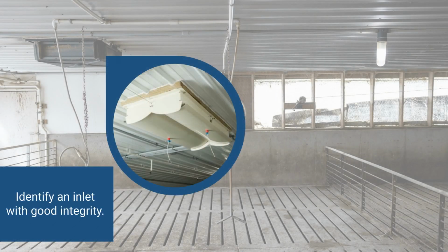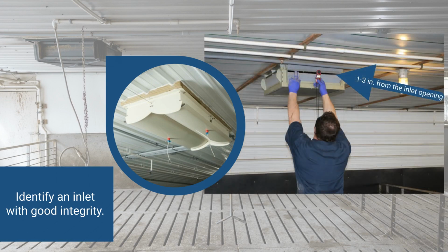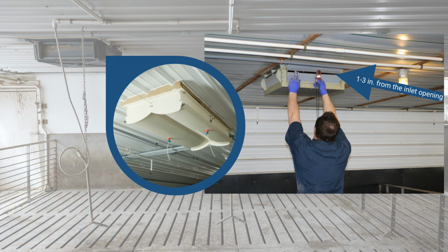To measure airspeed at the inlet, identify an inlet inside the barn with good integrity. Hold the anemometer 1 to 3 inches from the opening of the inlet so that the airstream blows through the vanes of the anemometer. If the opening of the inlet is narrower than the vanes on the anemometer, manually open the inlet to ensure sufficient volume for an accurate measurement. This will not impact the overall airspeed for the barn and will allow for a more accurate measurement. You should now read and record the maximum airspeed displayed.